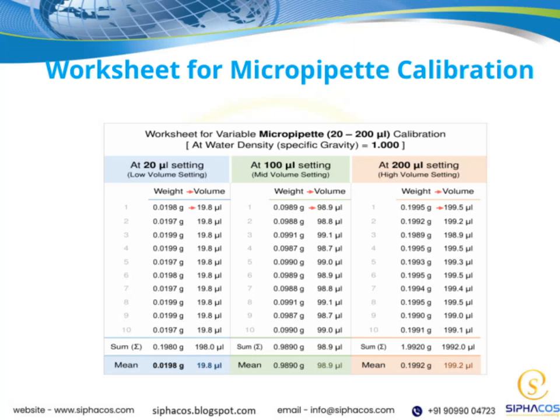Now, let's take a closer look at the worksheet for micropipette calibration. This worksheet is a practical tool designed to help us ensure our pipettes are delivering accurate and precise volumes. It typically includes steps for measuring the volume delivered, recording the measurements, and calculating the calibration factor. The key points to focus on here are understanding how to perform the calibration correctly, interpreting the results accurately, and knowing when to adjust the pipette to maintain proper calibration.